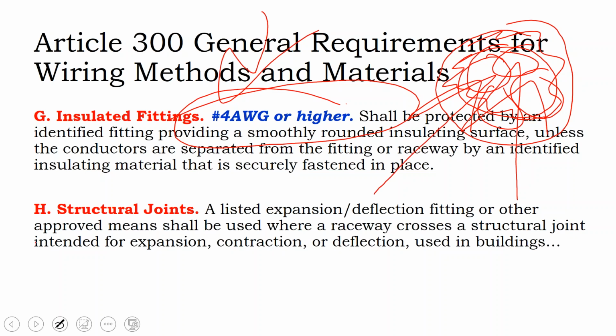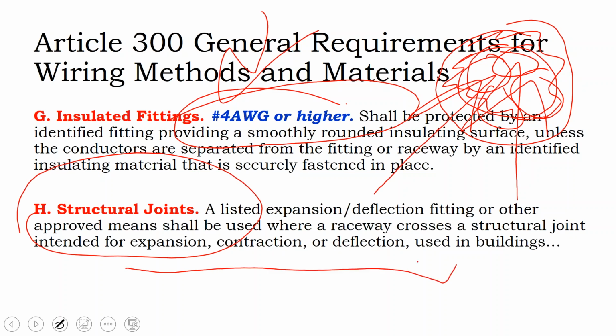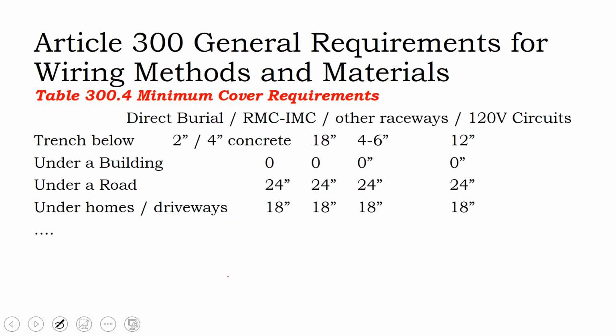We have a requirement for expansion and deflection fittings where your solar array may be intended to expand over long distances, and if you're not putting expansion fittings into your conduit, it can rip apart and start eating into your wires. Not that you can't pull your wires apart either, but you're reducing the safety risk substantially by using expansion fittings.